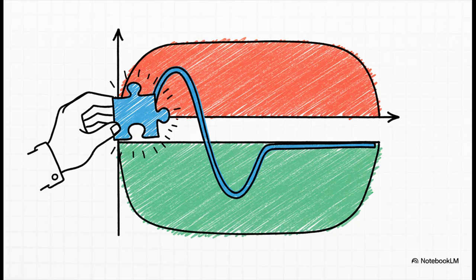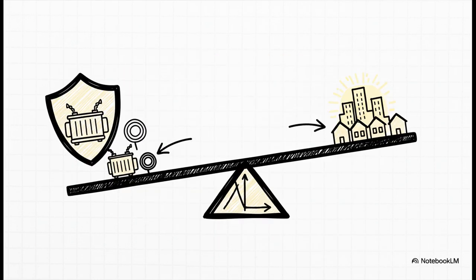So the entire job of a protection engineer is to solve this one big puzzle. They have to program the protective relay's inverse time curve so that it sits perfectly in that gap. It has to always operate before the equipment's damage curve is ever reached, but it must never operate during just normal, everyday conditions. And this right here, this is what that perfect balance looks like.